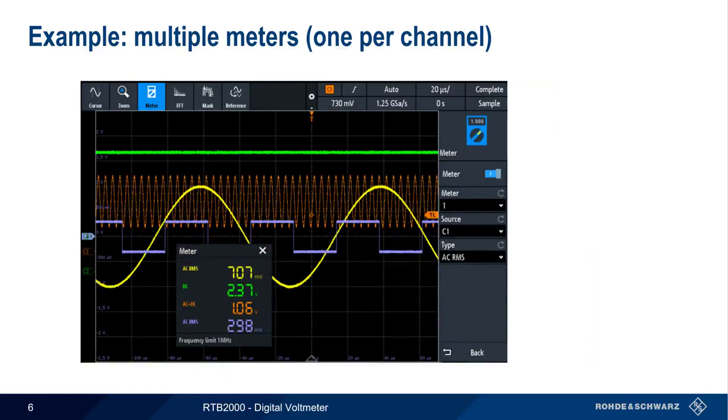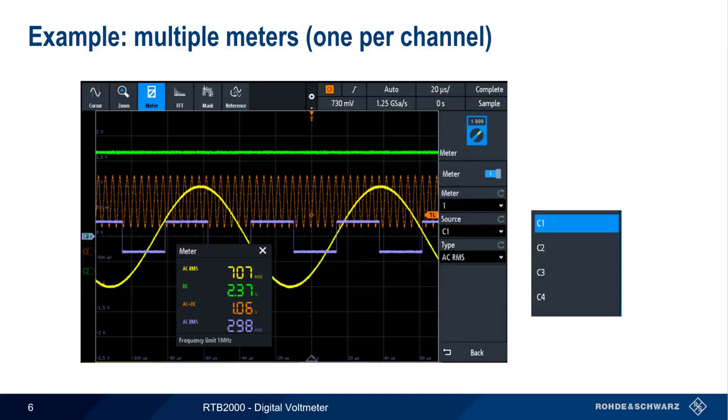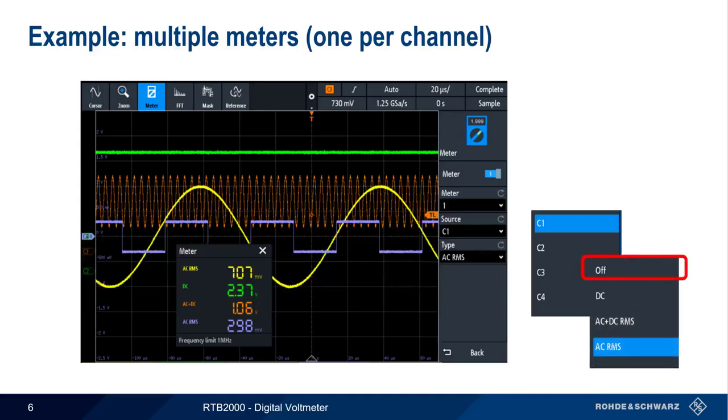As mentioned earlier, the RTB supports up to four simultaneous instances of the digital voltmeter. Here, each of the four voltmeters has been assigned to a different channel, with different measurement types being used for different types of signals: AC RMS on channel 1, DC on channel 2, AC plus DC on channel 3, etc. To turn off any of these measurements, we would simply set the type to OFF.